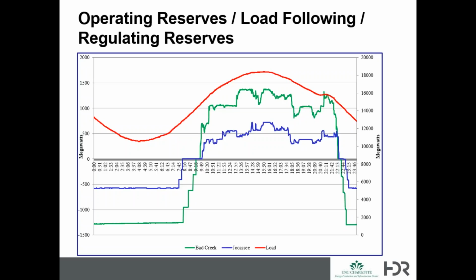Then they're brought online as generators at about 9 o'clock in the morning, generating throughout the day, following load and frequency regulation. Then you have load peaking in the afternoon, dropping off in the day - generation drops off, and when load really drops off after about 8 o'clock at night to midnight, you turn them around. They're only idle about 10 minutes, then you change direction, bring them on in synchronous condense in pump mode, and load them as load decreases.